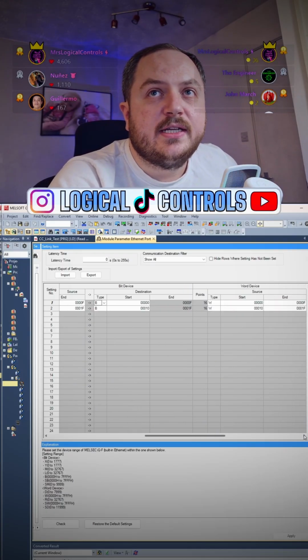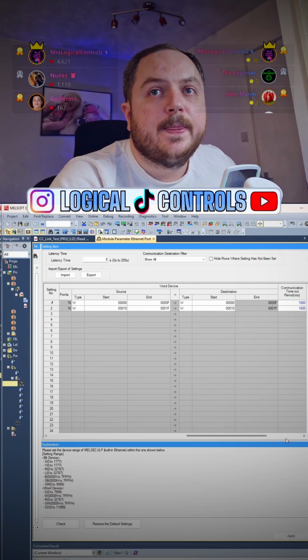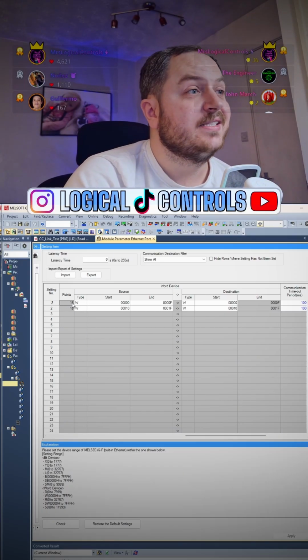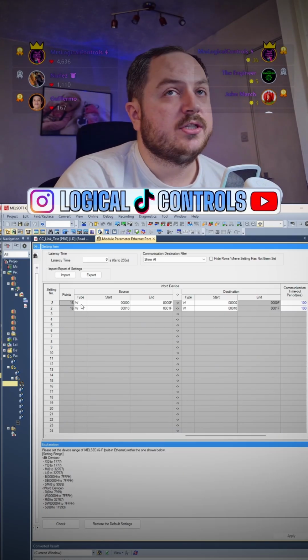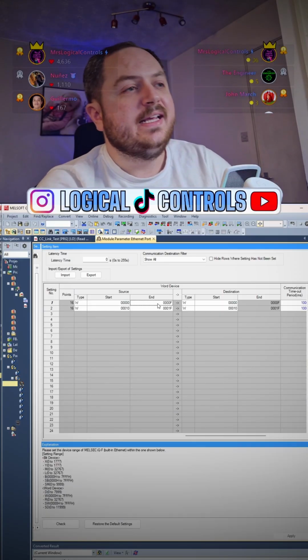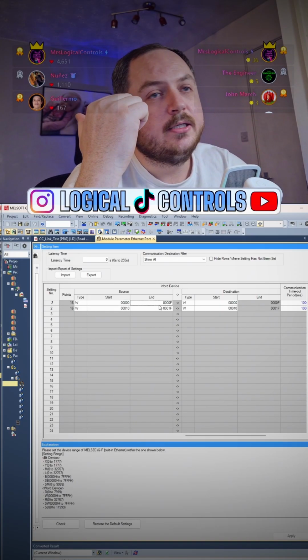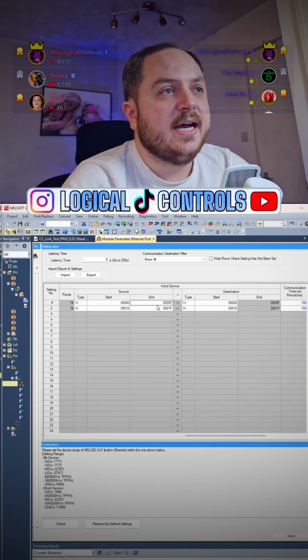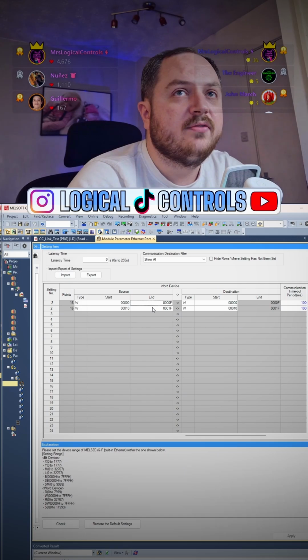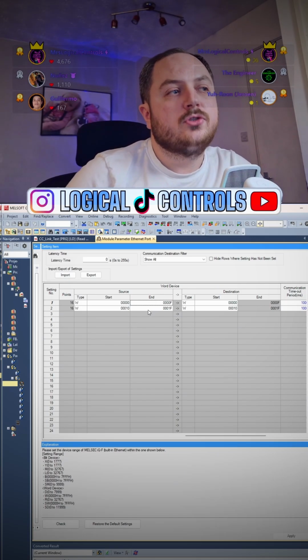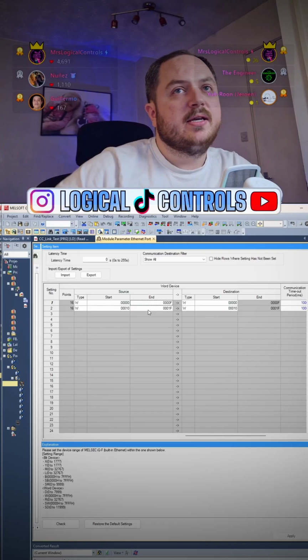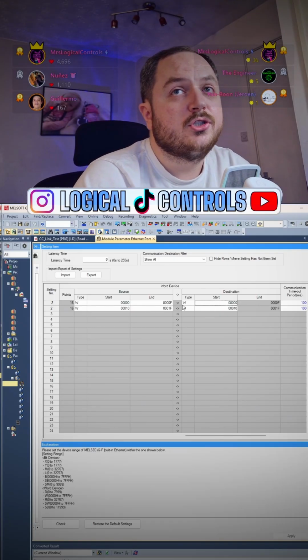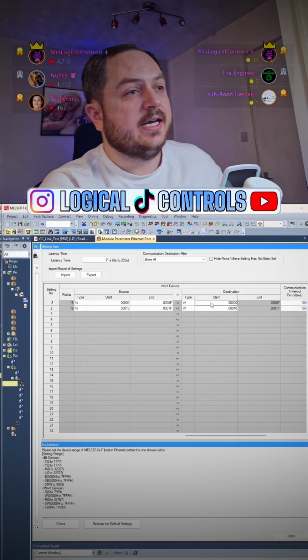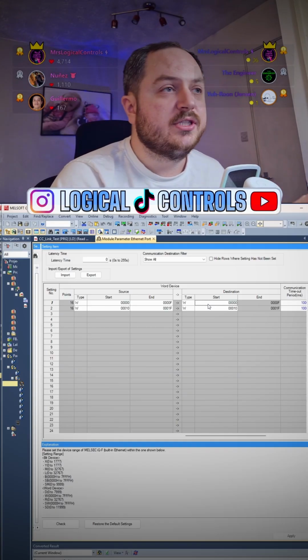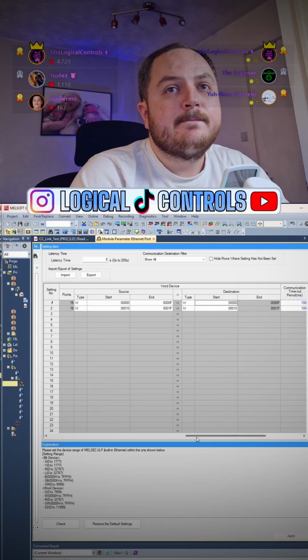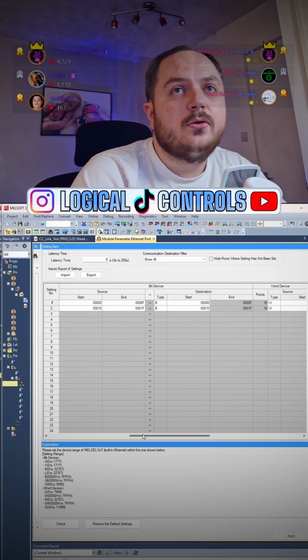I'm also reading some word registers, or 16-bit registers, and I'm reading 16 of those. Those are W registers, and I'm reading 0 to F again. So any values in the other PLC, say if it has a temperature sensor or a level sensor or something like that, it could store them in those W registers, and they would get read into this PLC also. And again, I'm just storing them in the same place that I read them from. So this PLC and that PLC both have the same W0, the same W1, whatever it is. And that's the reading part.